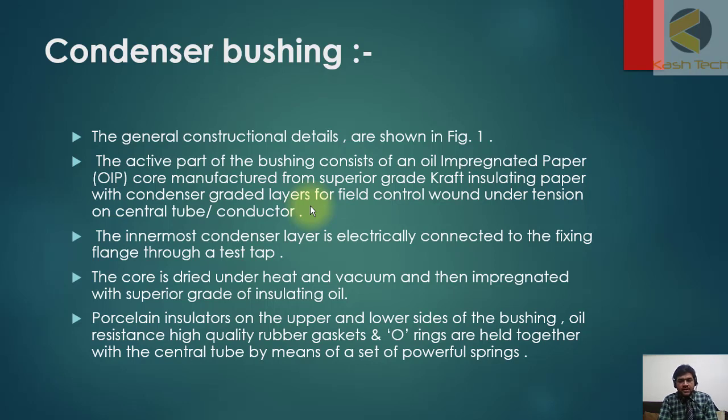Wound under tension on a central tube condenser conductor, the innermost condenser layer is electrically connected to the fixing flange through a test tap. The core is dried under heat and vacuum and then impregnated with superior grade of insulating oil.